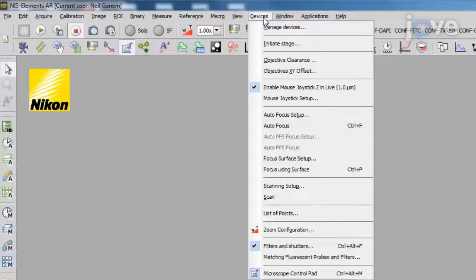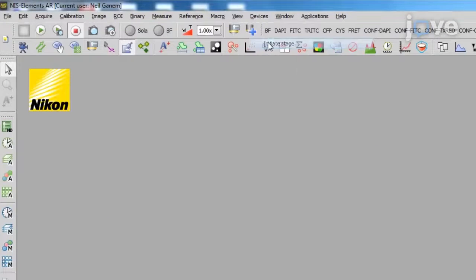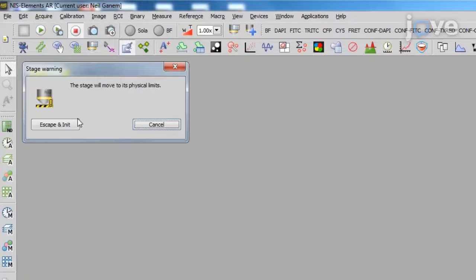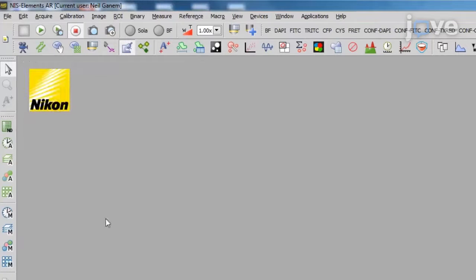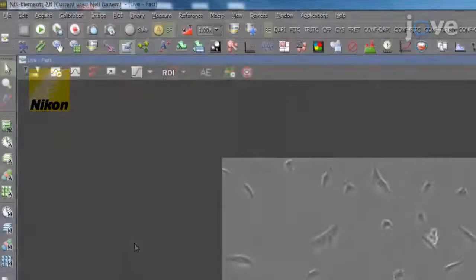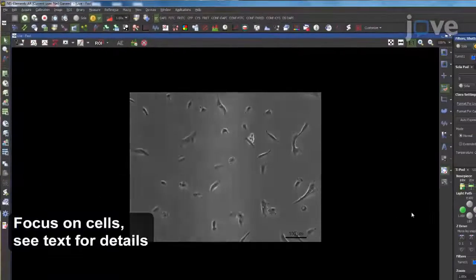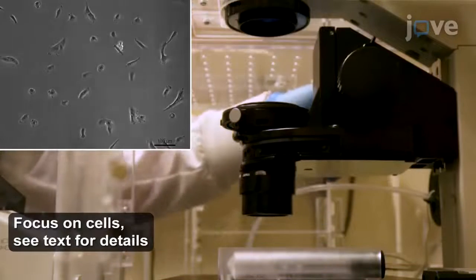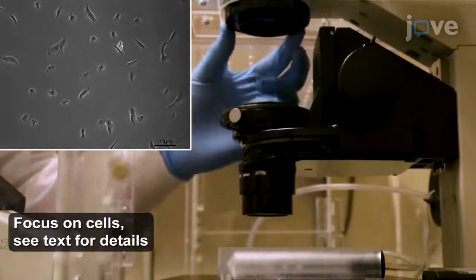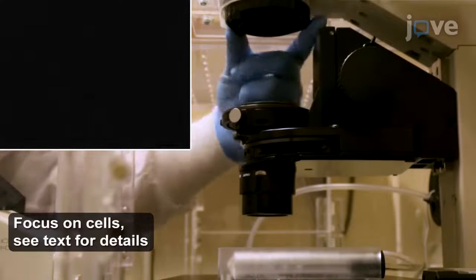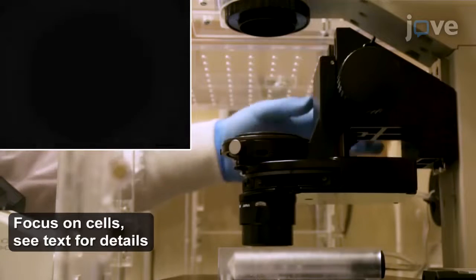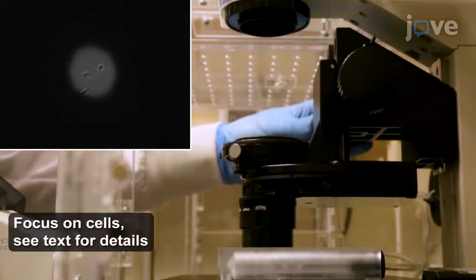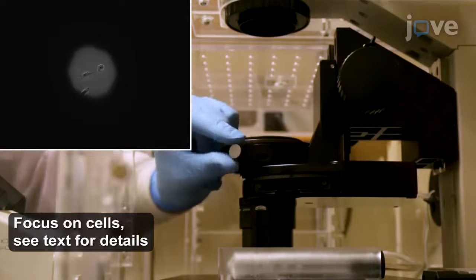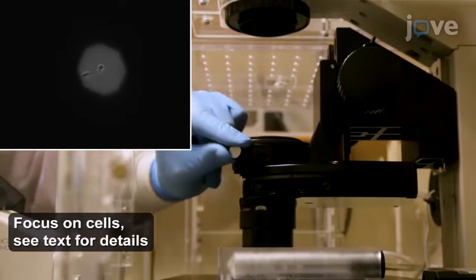Initiate and calibrate the encoded stage using the software program controlling the microscope. This will ensure accurate XY coordinates and prevent focal drift. Next, perform the Köhler illumination by raising the condenser and closing the aperture so that the field is dark. Lower the condenser until a crisp hexagonal shape of light is visible. Then, use the centering screws to center the hexagon of light in the field of view.